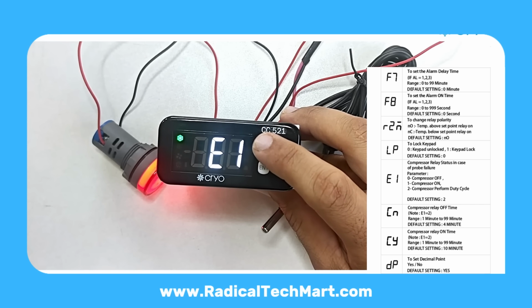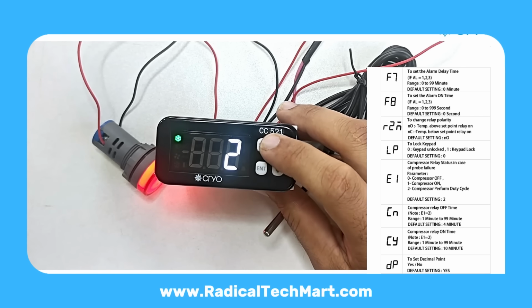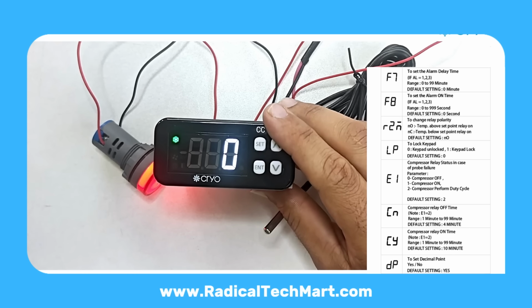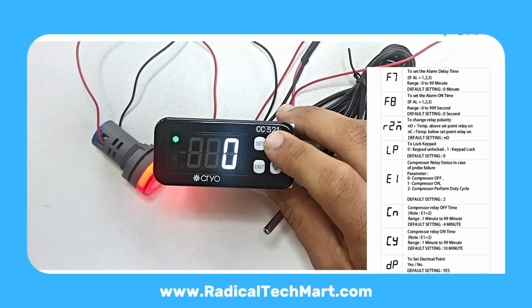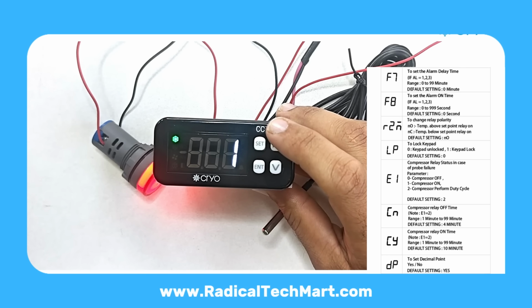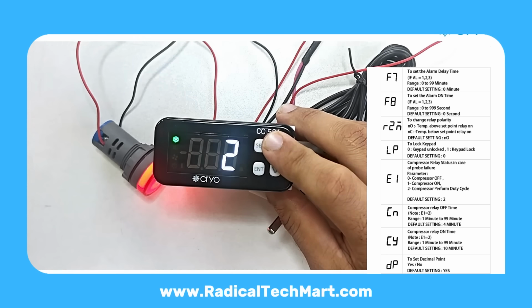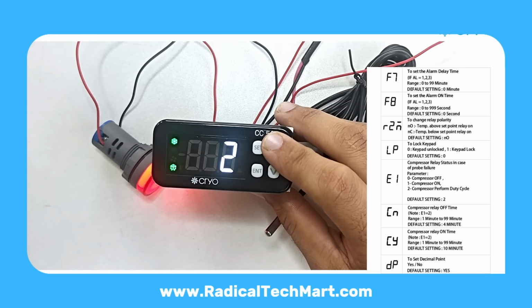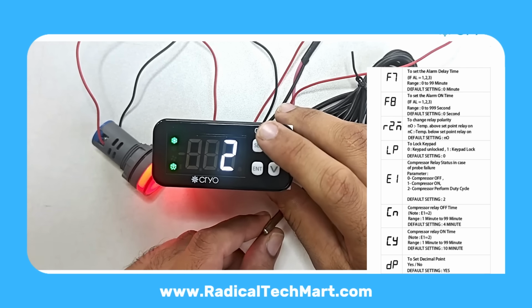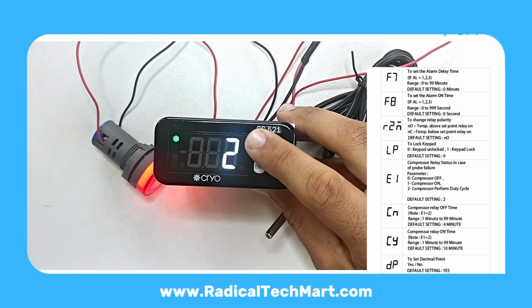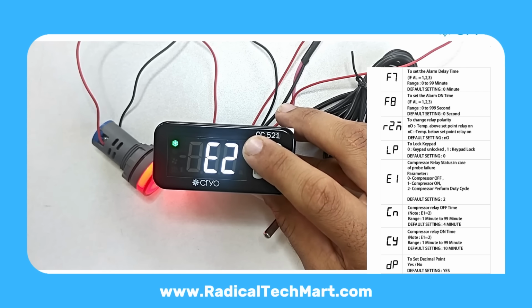Next, E1 Compressor Status on Probe Failure. 0 is equal to compressor always off, if sensor fails. 1 is equal to compressor always on. 2 is equal to duty mode, on for 10 minutes, off for 4 minutes cycle. Choose according to your safety requirement.